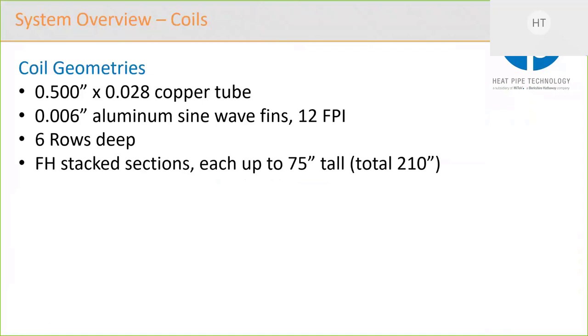So you can get the coils in sections up to 75 inches tall. And the total height is 210 inches, and that's based on the largest skid that I mentioned before, which is actually 210 gallons per minute as well.